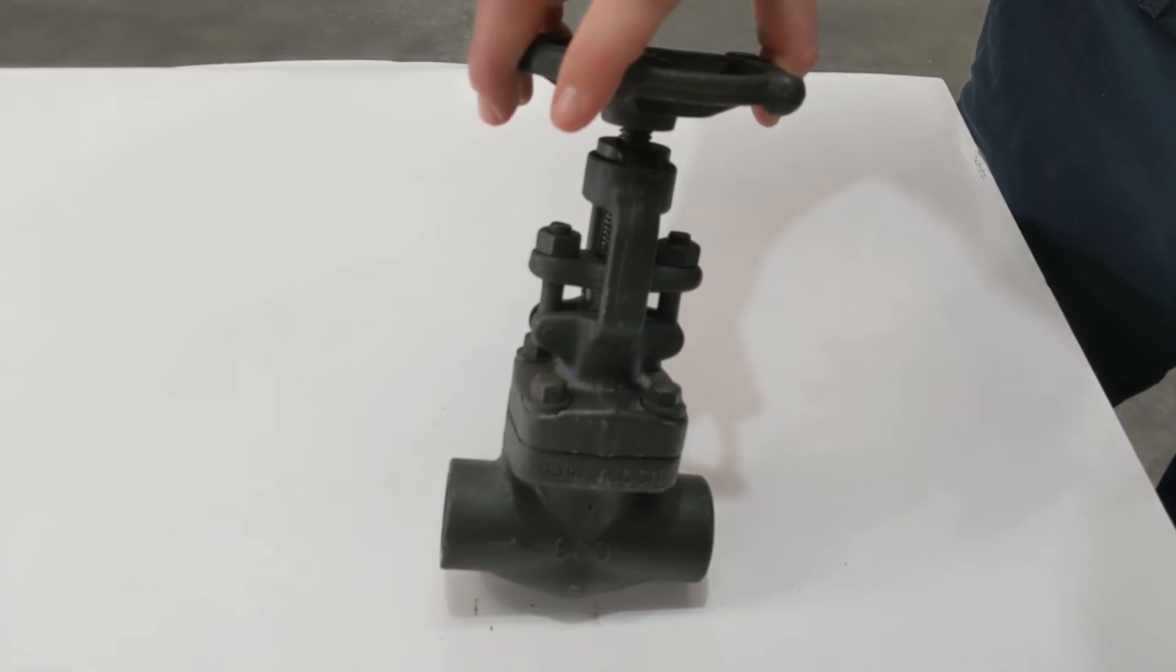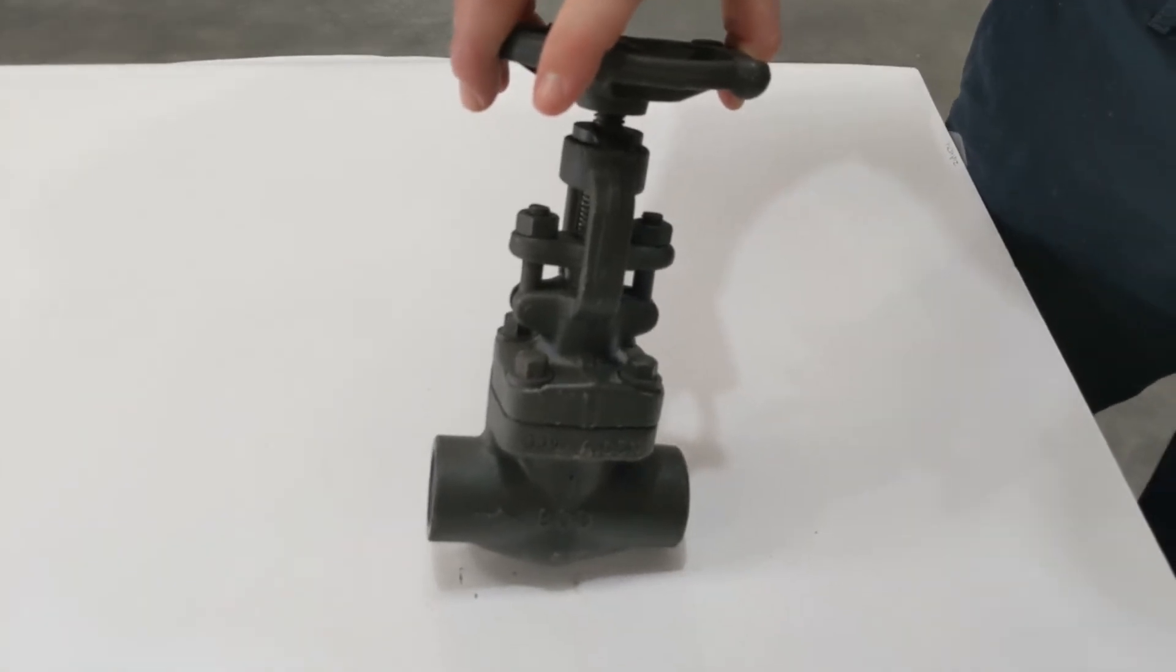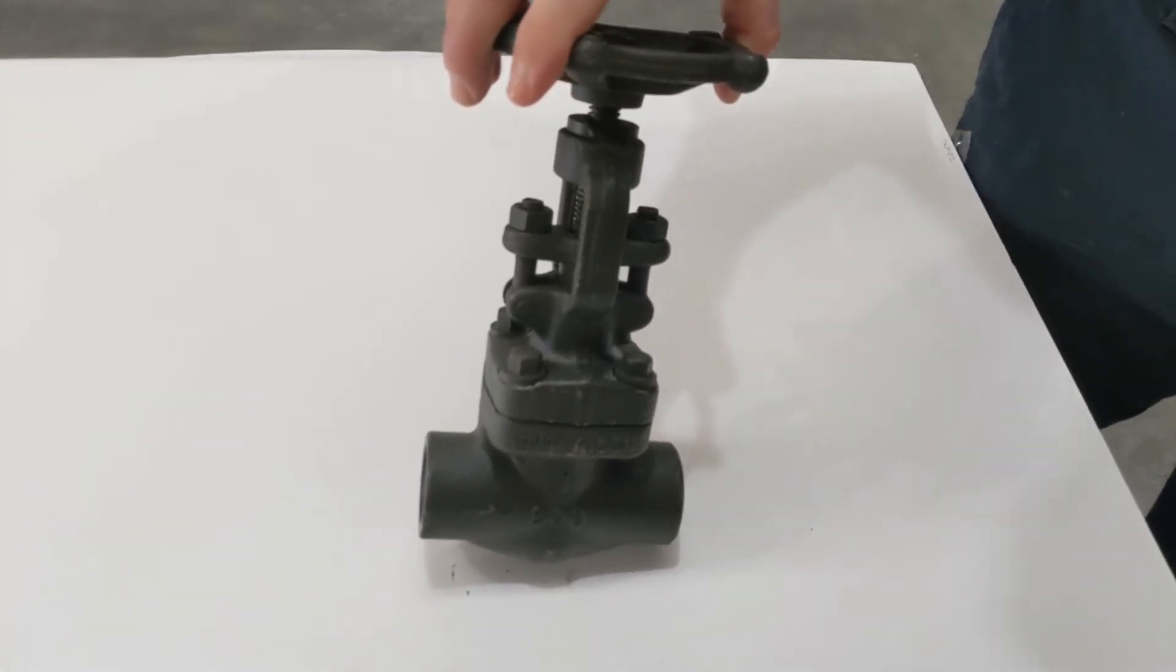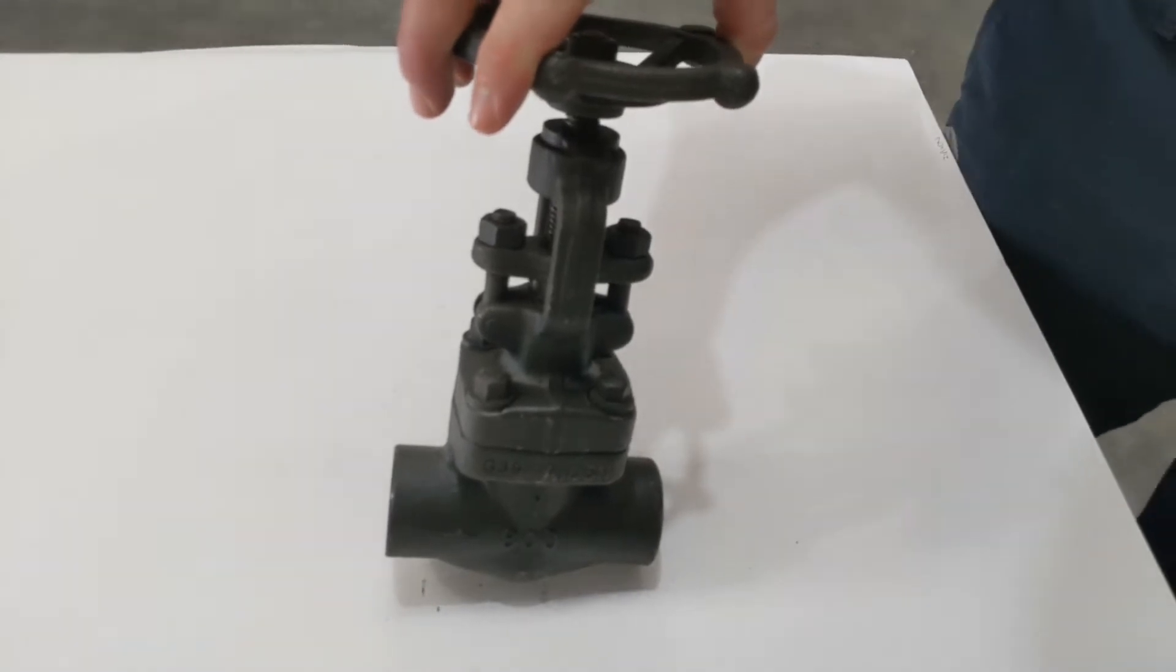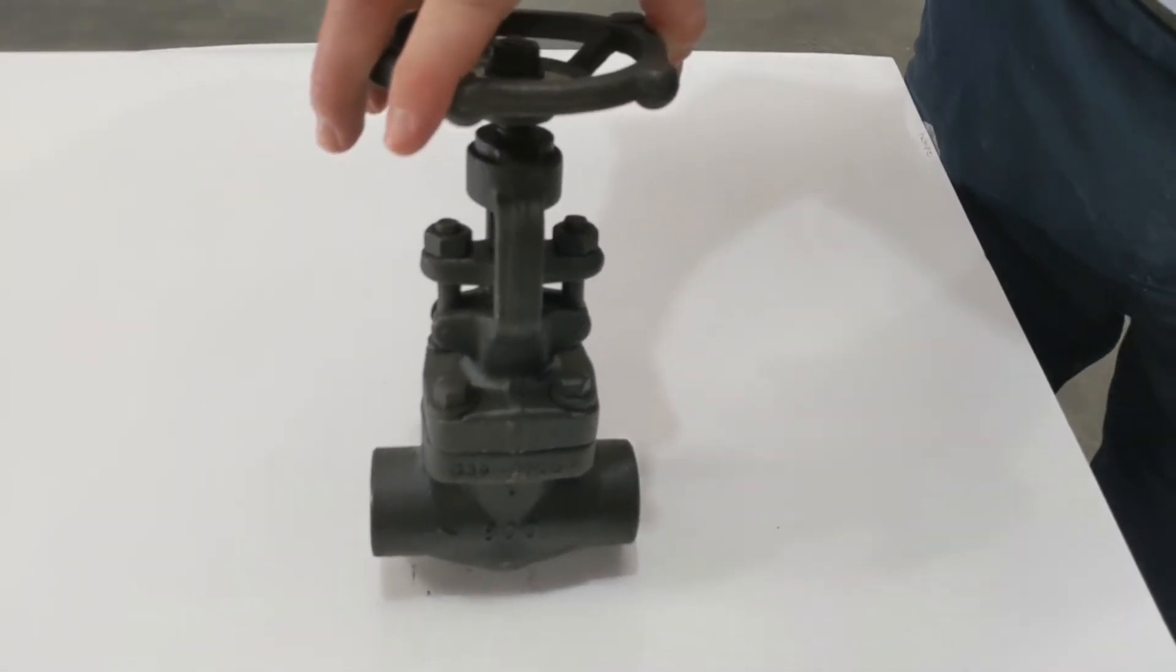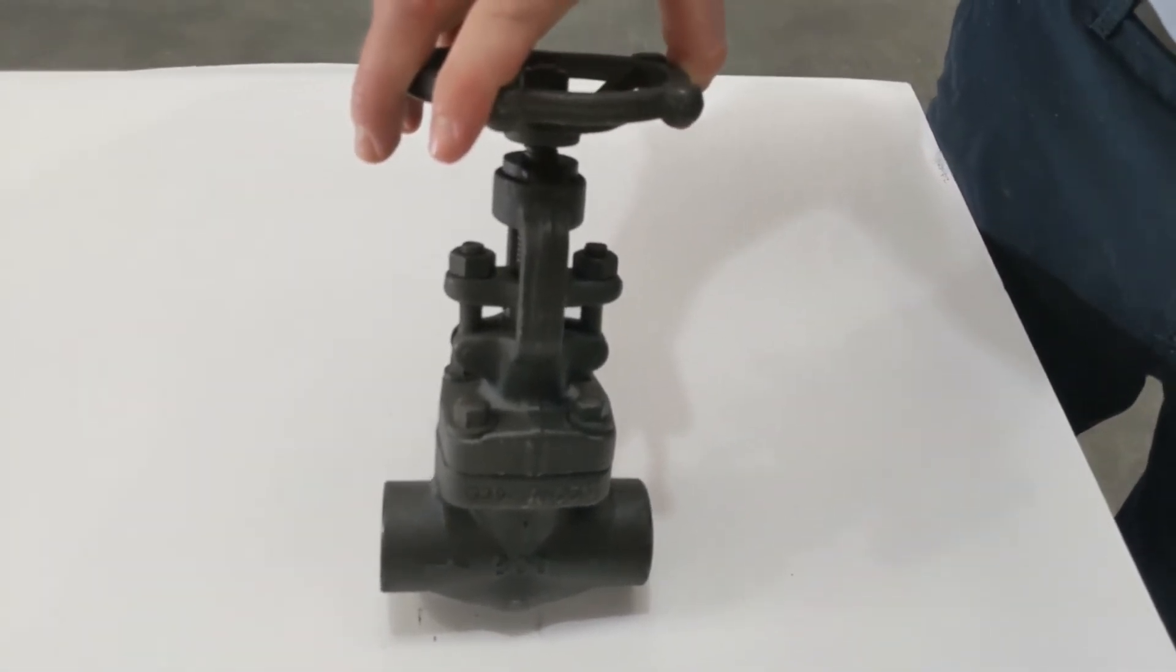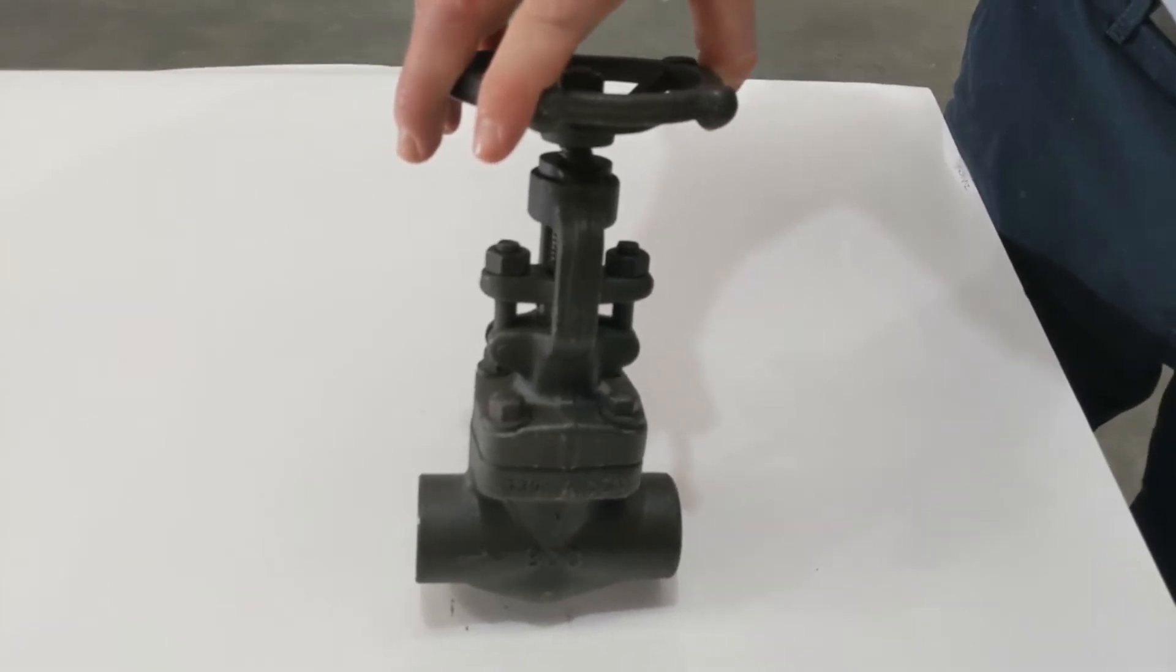Not like a gate valve or a ball valve where you get maybe three quarters of your flow in the first quarter of opening. So the flow is proportional all the way up, and of course you can go from a very low flow to a large flow because of the ball, is that correct?